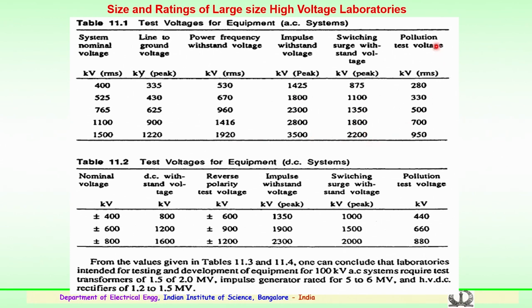For pollution or contamination, very important, as the voltage level goes higher and higher, EHV and UHV, contamination or pollution is a very important criterion to be considered for the design applications. Here, for 400 kV the withstand for pollution or contamination is 280 kV. In case of 765 kV it is 500 kV, in case of 1100 it is 700 kilovolts, and for 1500 it is 950. These are the various values for the power frequency, lightning impulse, switching impulse and pollution test withstand voltages.